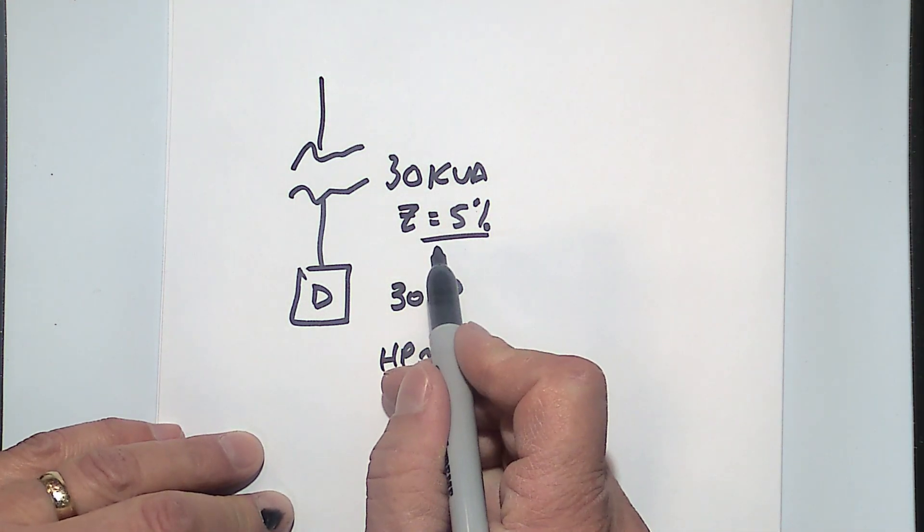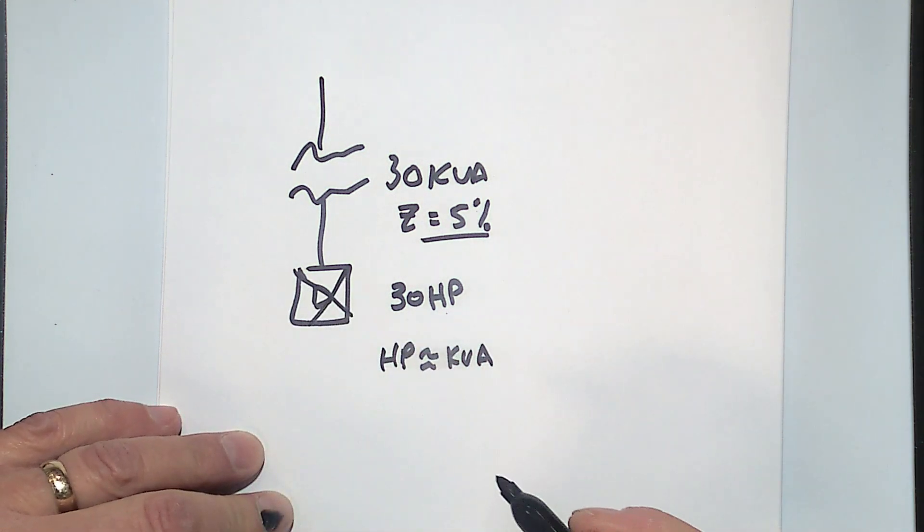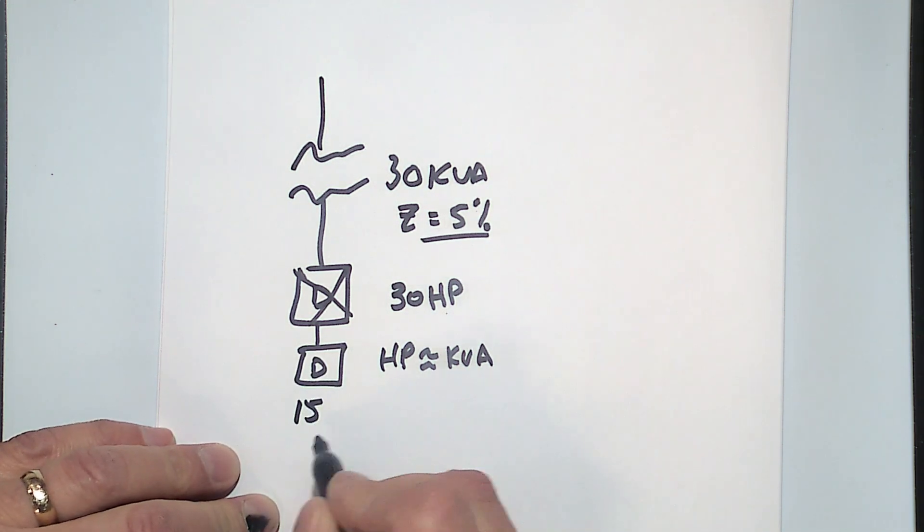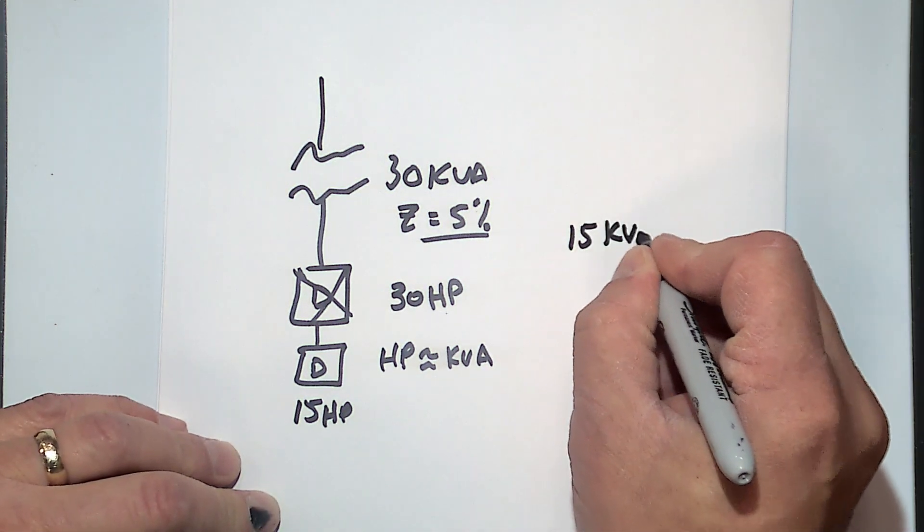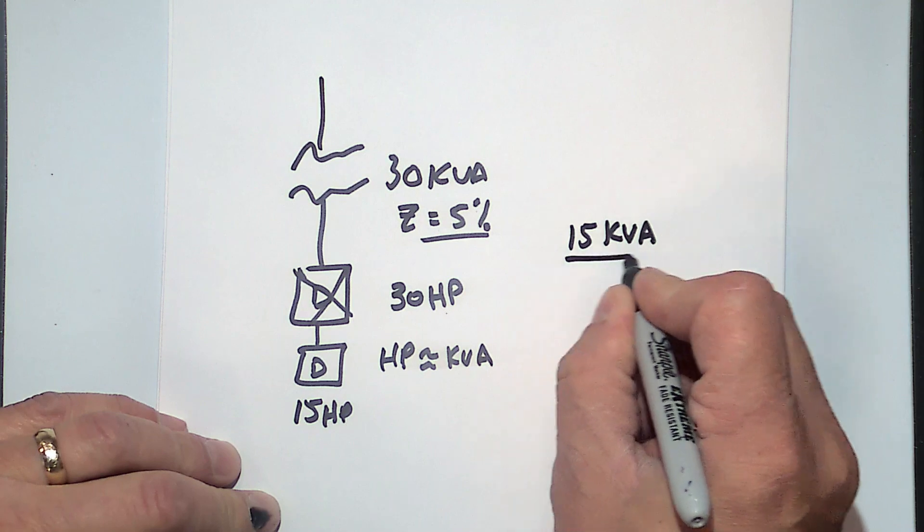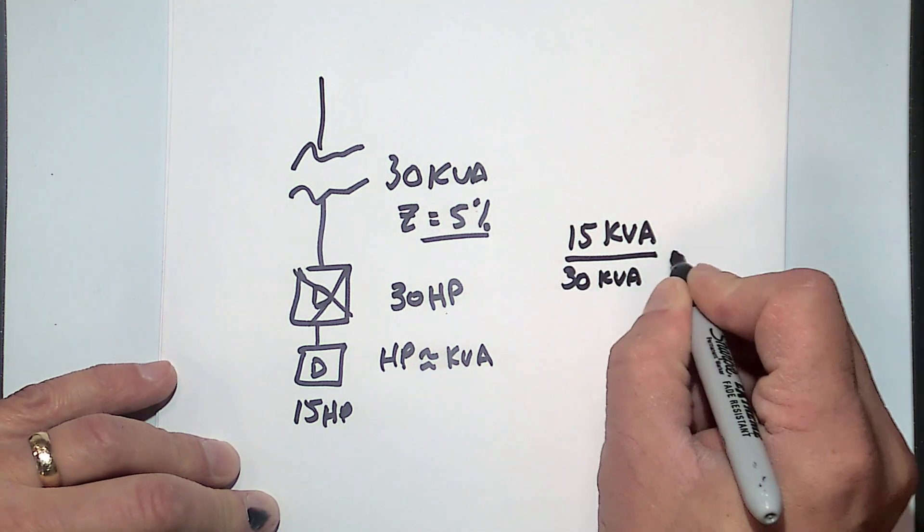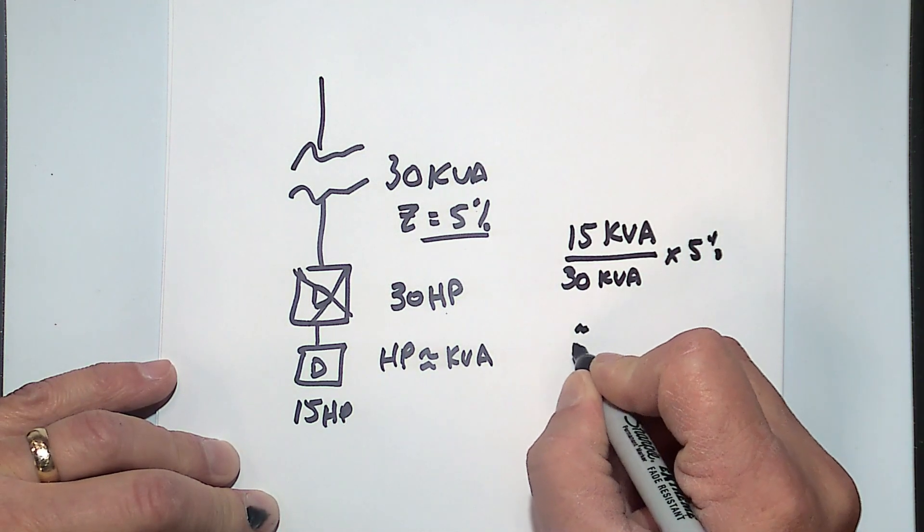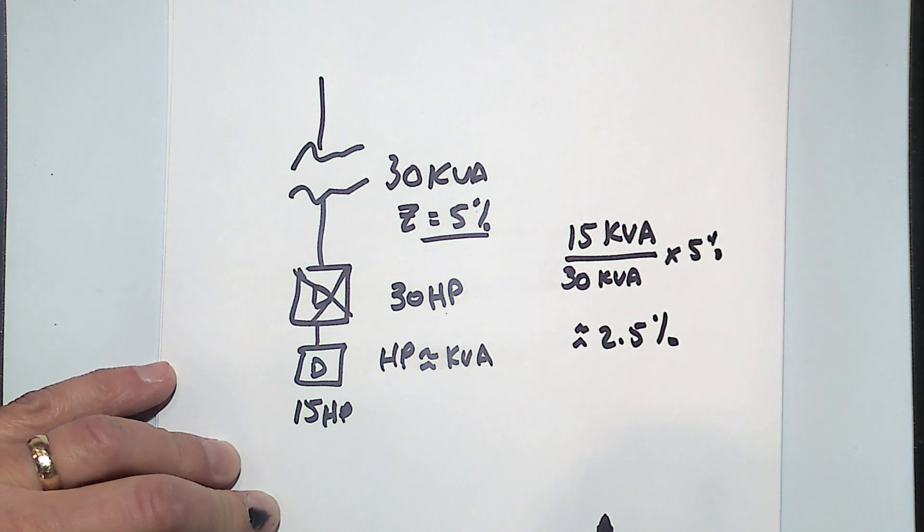But what happens is, what if this drive is not 30 horsepower, what if I have a 15 horsepower drive here? Well, the equivalent impedance then would be 15 kVA, because we said kVA is equivalent to horsepower, over 30 kVA, times the 5%. So I'd effectively get about 2.5% impedance or reactance in front of that drive.